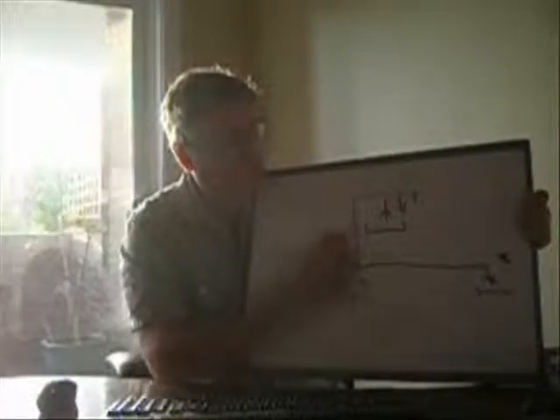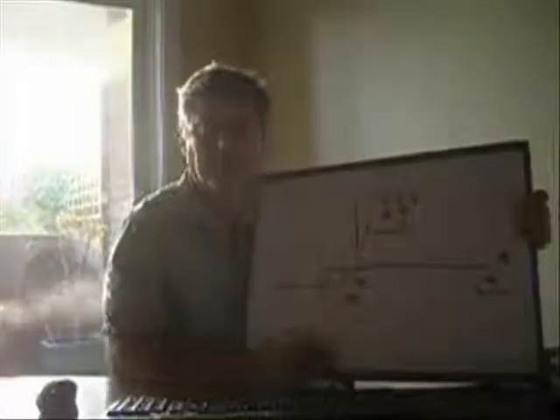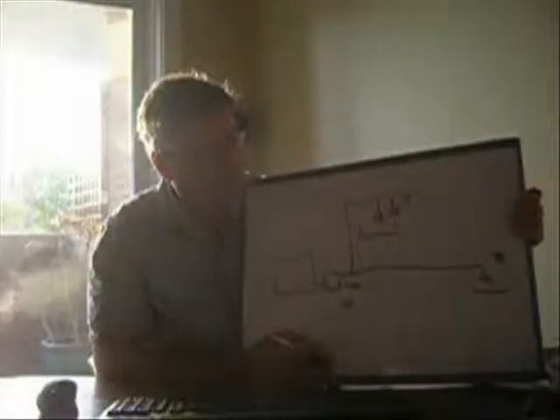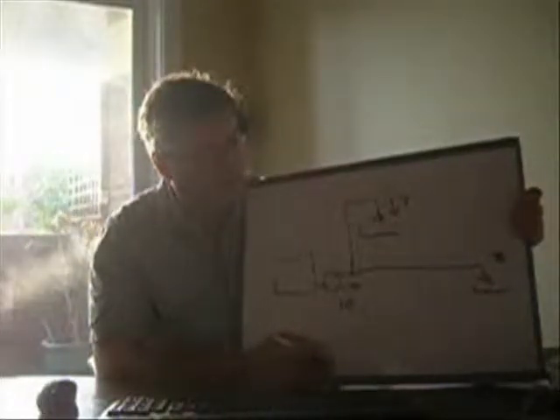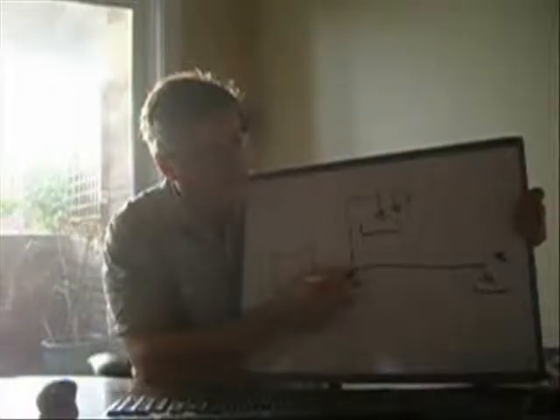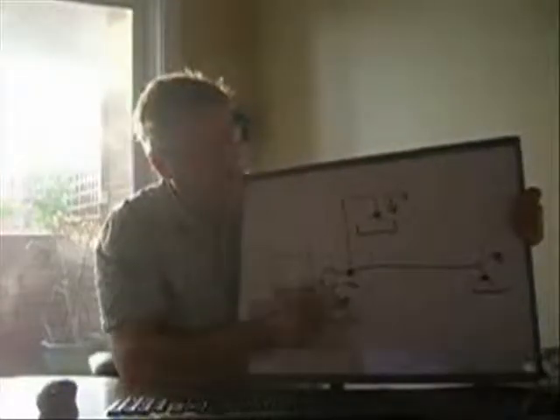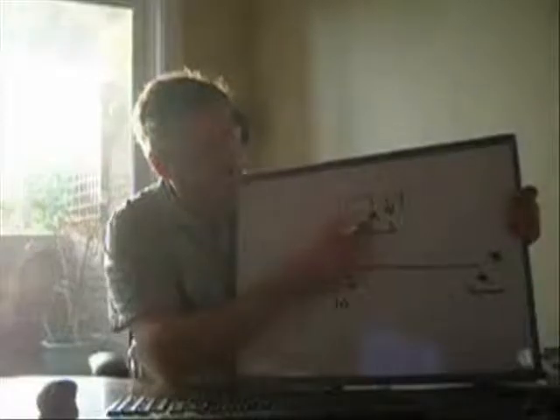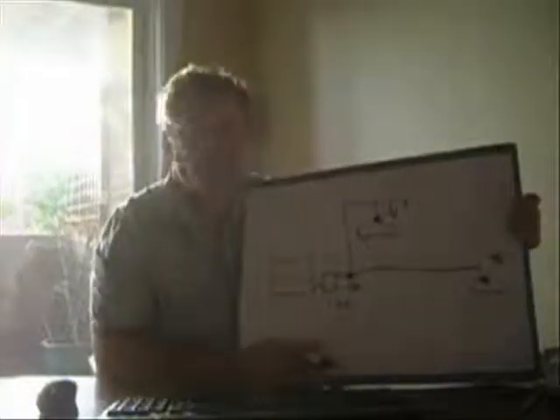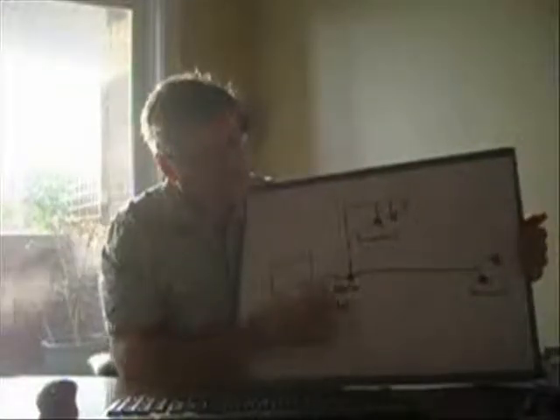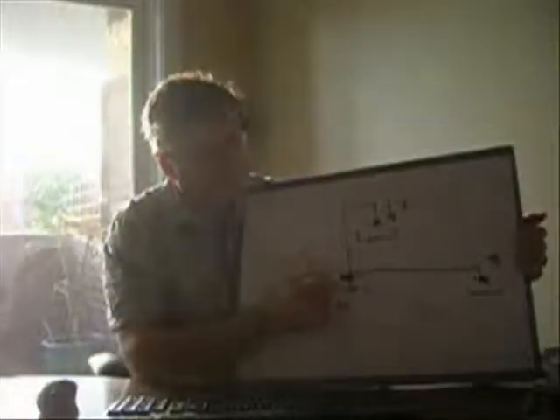Now, how do we ensure we're going to have seven here and three here? We're going to first calculate what the friction head is. We're going to take these points and do a calculation of friction head and static head for these two, for the flow that goes through this branch. And then we'll do a calculation for the flow that goes through this branch from this point to this point.